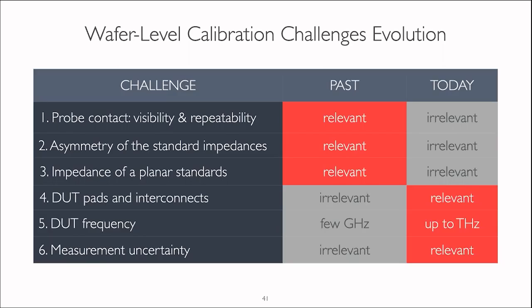When we do wafer level measurement, we usually measure port 1 and port 2 standards at once, and standards are represented by two physical elements, like a pair of opens, a pair of shorts, and a pair of loads. And if you cannot position the probes on the standard accurately, your standard electrical characteristics become asymmetrical. That was a big problem at the beginning of the on-wafer measurement history, and today it becomes less relevant because engineers found a very good solution. Impedance of the planar calibration standards.